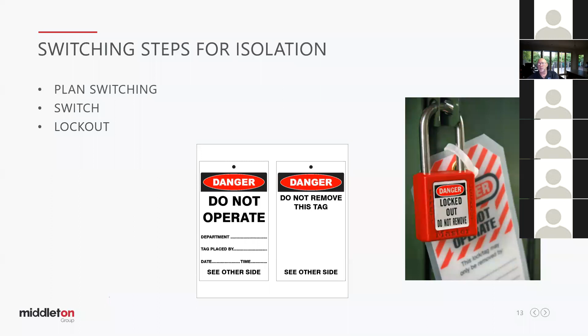So once you've switched and locked out, you need to prove dead, or confirm you've de-energised. How do you do that? For HV, you usually use a non-contact tester, which senses electric field.